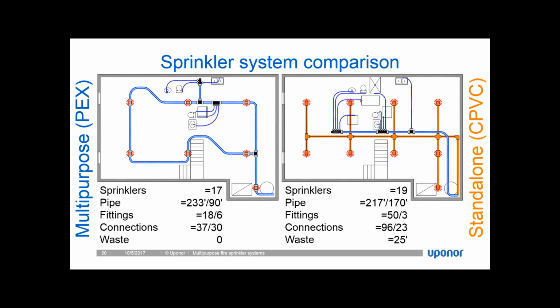So flow at the furthest point, maybe that requires a little bit of clarification. For the fire sprinkler, there is a specific amount of flow that each sprinkler needs to operate properly, and those are detailed in the requirements of 13D and also the sprinkler manufacturer's listing. Okay. So it's not just about water coming out of the sprinkler. It's the right amount of water.